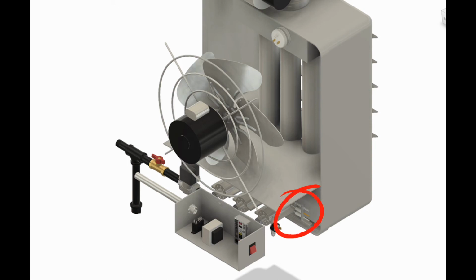You can also see here, this is your pilot assembly. So you may have a standing pilot on older units. You may have a pilotless ignition, a spark igniter, or a hot surface igniter. This one has a pilot tube, a spark igniter, and then a flame sensing rod. So once the pilot light lights, that flame sensing rod again will induce a current and then open the main gas valve, and the rest of your burners will light. And then up here, this little round device is a pressure switch or air proving switch, and that just proves that the draft inducer fan is running.